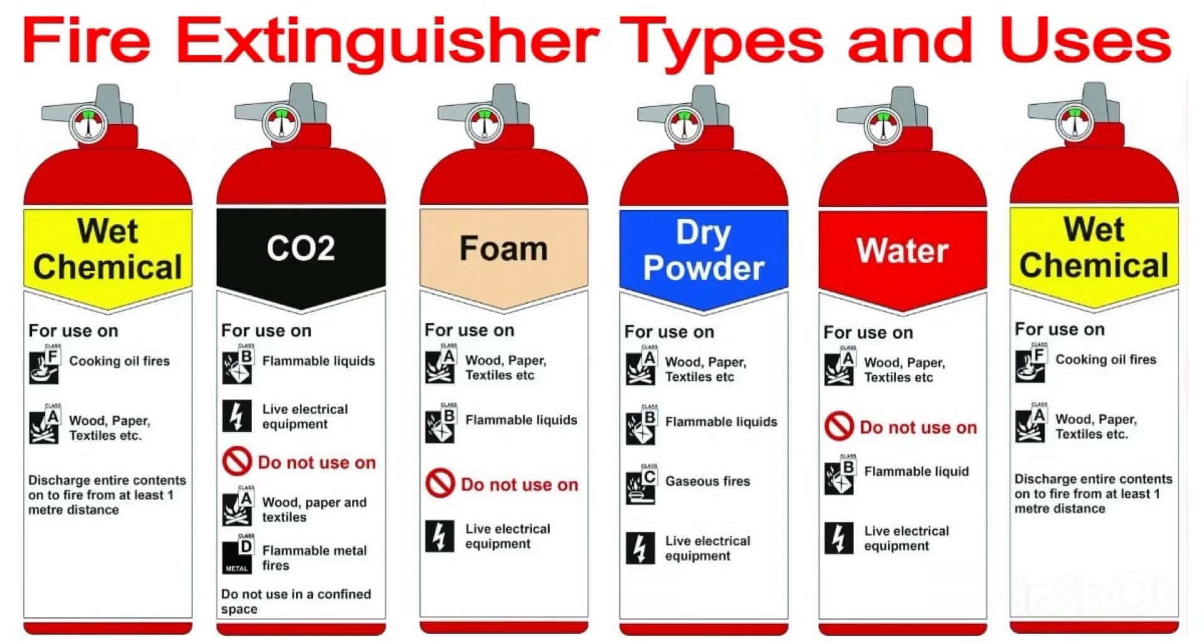If you use in confined space, if it is discharged in confined space, if you use carbon dioxide, there might be breathing problems. Third, foam type fire extinguisher for use on class A fire and class B fire: wood, paper, textile and flammable liquids like diesel, petrol, paint, etc.